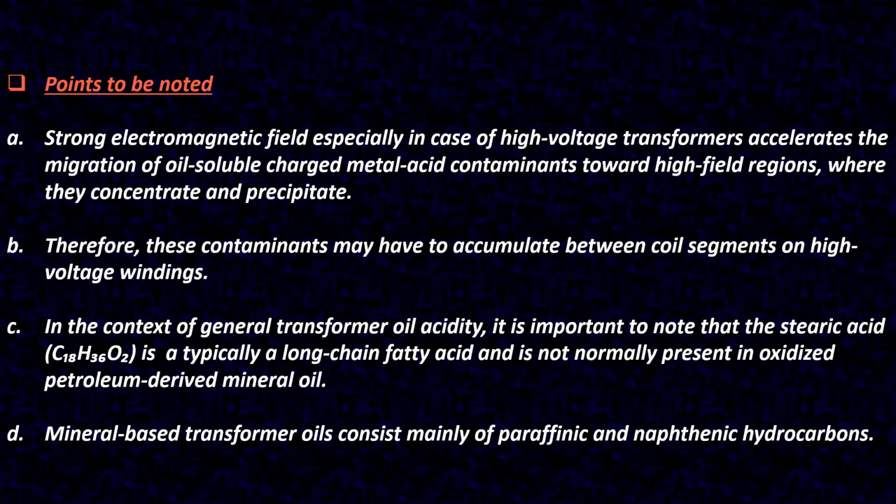In the context of general transformer oil acidity, it is important to note that stearic acid, C18H36O2, is typically a long chain fatty acid and is not normally present in oxidized petroleum derived mineral oil. It is actually exhibited in vegetable oil.